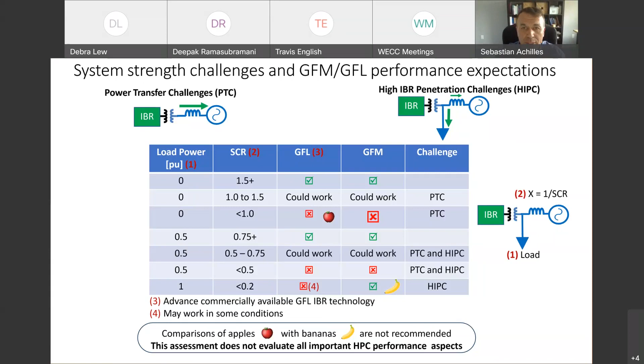Now, the other comment related to the box below is that this assessment of faults and fault recovery is what we're accustomed to doing in the context of power transfer challenges, particularly for the first 3 rows. When we look at grid forming, this is only a part of the things that we should look at, because grid forming is supposed to differentiate with respect to grid following in other aspects, not necessarily in these ones. Thank you. Can we move to the next slide, please?